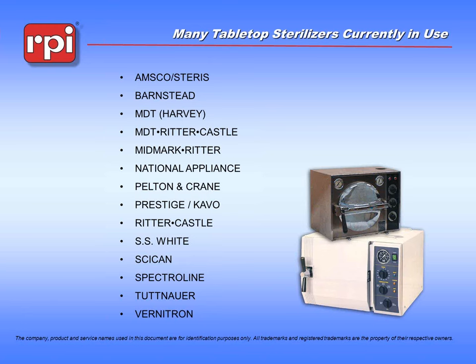To start the history of the tabletop sterilizer, we can trace it back to the 1600s when a product named the digester was being produced. The digester was used in the food industry as a cooking device and is still in production today as a pressure cooker. Basically, you had a sealed vessel that could be opened and closed at will. You would put water and food in it, put it on a heat source, which would boil the water creating steam, and the steam was contained within the pressure vessel, increasing the pressure and decreasing the cooking time.